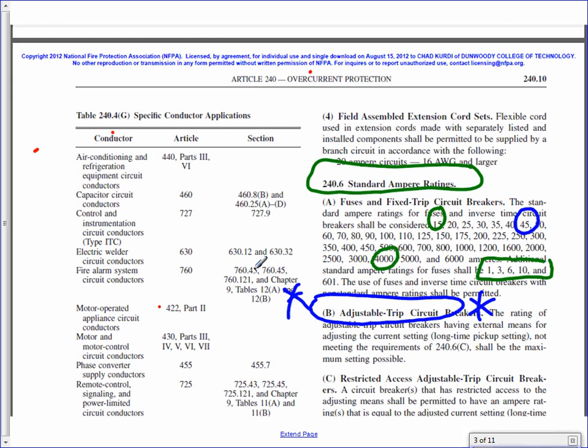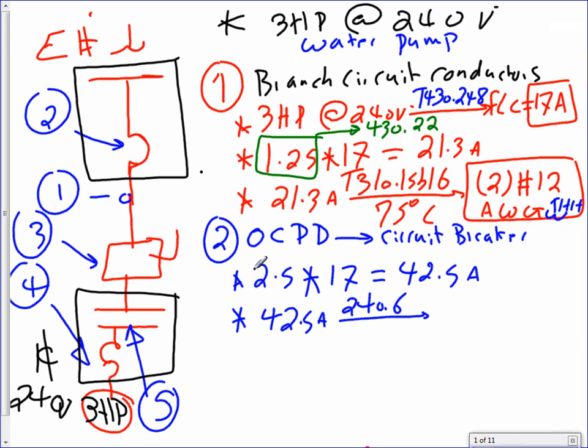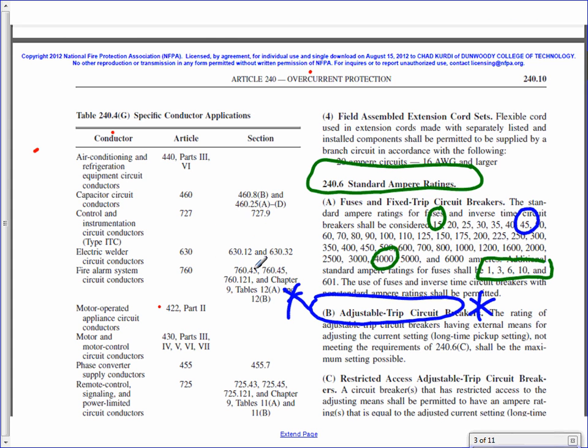I think I have it here. There you go, 240.6. I want to remind you, my math came up to 42.5 amps. I need to size the circuit breaker, so you're going to take it to 240.6. It says fuses and fixed trip circuit breakers. Here are all the sizes that we use in the US. We start from 15 and go all the way to 4,000, even to 6,000. The most common is up to 4,000. You can have 1, 3, 6, 10 fuses. These are the standard size fuses that we use in the US. Non-adjustable trip circuit breakers are right here, guys. Leave this one until the commercial industrial project. We will be using the bottom one, the B, later on. So we're now in the A's.